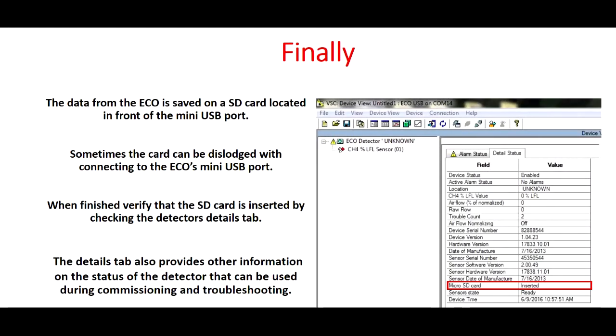The data from the ECO is saved on an SD card located in front of the mini USB port. Sometimes the card can become dislodged when connecting to the ECO's mini USB port. When finished, verify that the SD card is inserted by checking the detector's Details tab. The Details tab also provides other information on the status of the detector that can be used during commissioning and troubleshooting.